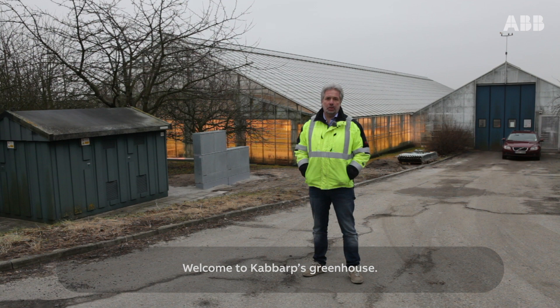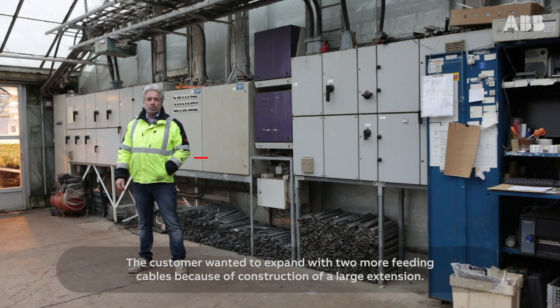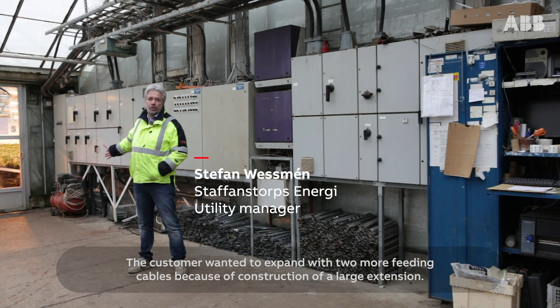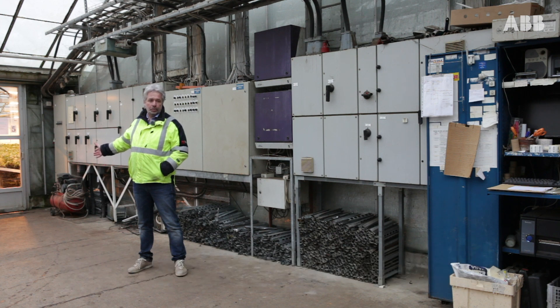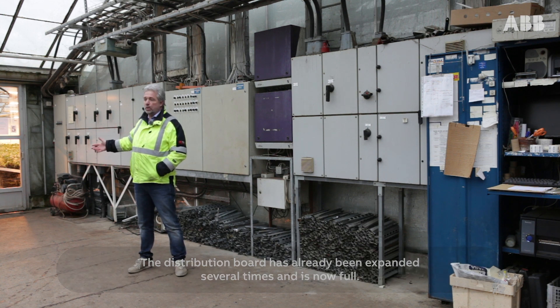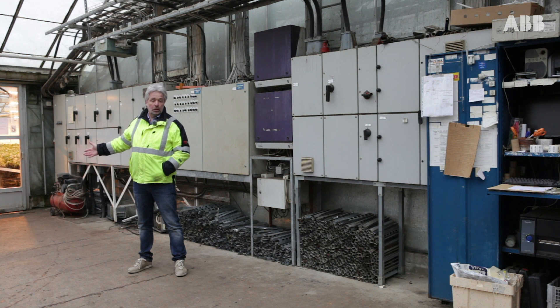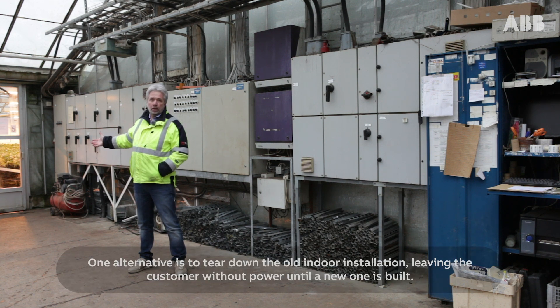Welcome to Kabbarp's greenhouse. The customer wanted to expand with two more feeding cables because of construction of a large extension. The distribution board has already been expanded several times and is now full. One alternative is to tear down the old indoor installation, leaving the customer without power until a new one is built.